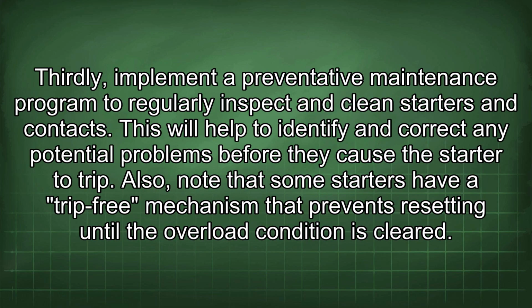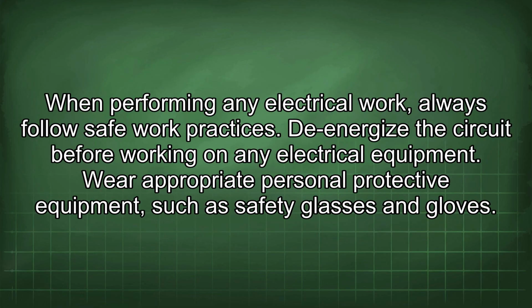Thirdly, implement a preventative maintenance program to regularly inspect and clean starters and contacts. This will help to identify and correct any potential problems before they cause the starter to trip. Also, note that some starters have a trip-free mechanism that prevents resetting until the overload condition is cleared. When performing any electrical work, always follow safe work practices.